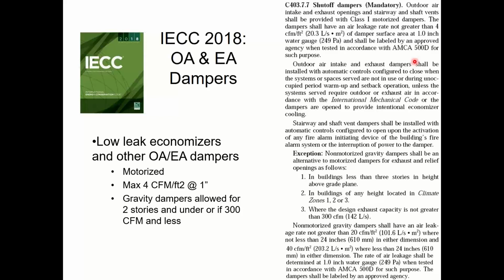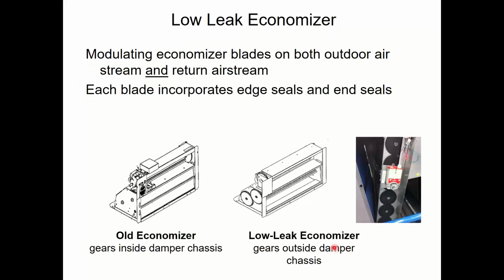I'm sure they're going to leapfrog us again because they always do that, but that's how it goes out there. There are some exceptions to when you don't have to do this, but as soon as there's a motor on there, you have to do it. And all economizers have a motor, so for all economizers, they have to be low leak. From a visual standpoint, you can easily tell for most systems, rooftop systems, if you have a low leak.